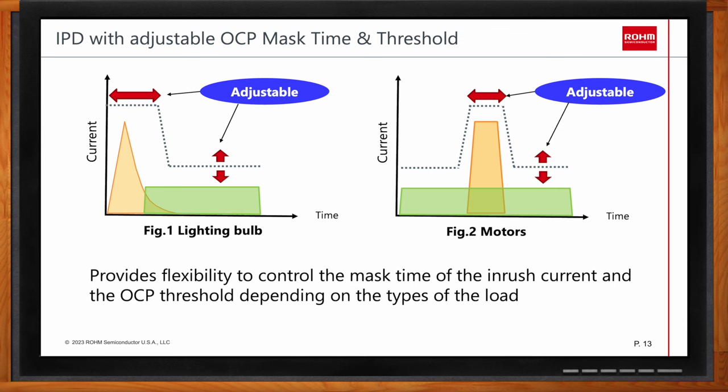There are two operating examples when A-OCP and adjustable OCP mask time are integrated in the IPD. The first is a capacitive load such as lighting bulbs: the inrush current is protected by the internal OCP, while current during normal operation is protected by the A-OCP. The second use case is motor loads: the adjustable OCP mask time provides effective protection not only against inrush current during IPD startup, but also against motor lock current.